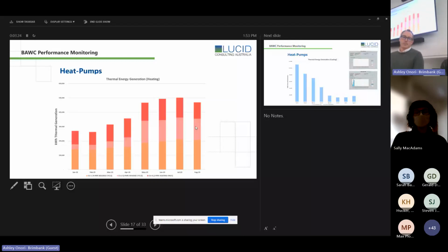So you can see that, what have we got here? The 4-pipe reverse cycle chiller is doing the bulk of the thermal generation for heating hot water. That's in the orange. You then have, these should be flipped around, the 2-pipe heating only heat pump, which is the red. That's doing the next. And then you've got the 2-pipe reverse cycle. That reverse cycle unit can flip into heating or cooling, depending on what the building needs, doing the top up. And as you'd expect, from January moving all the way through to August, you're seeing that massive ramp up in thermal energy demand, and that's purely just climate based, as we're moving into winter.